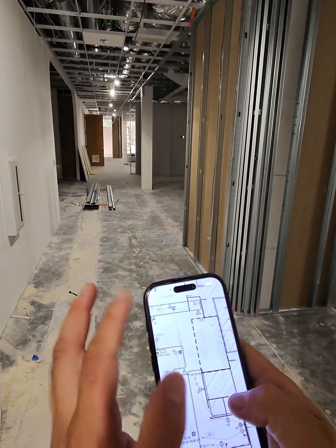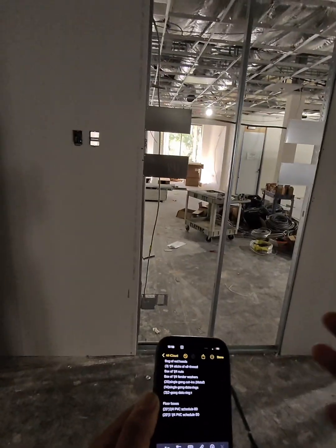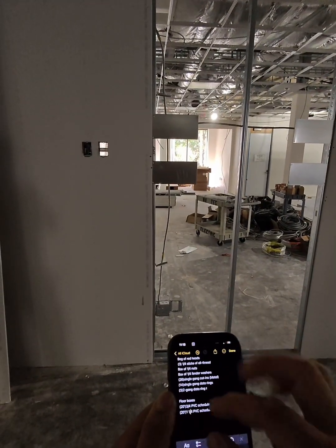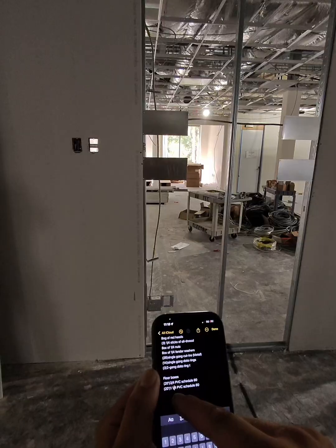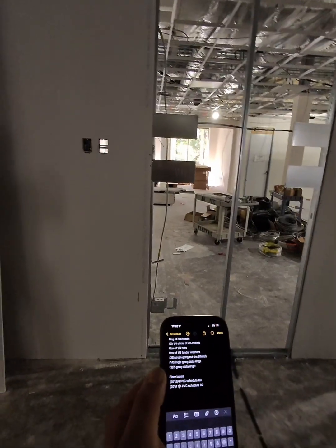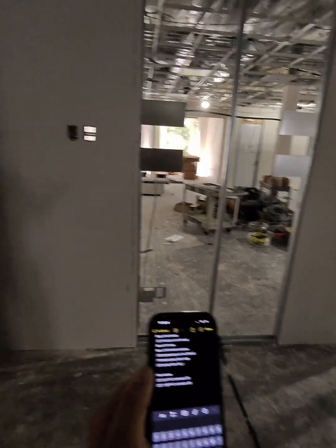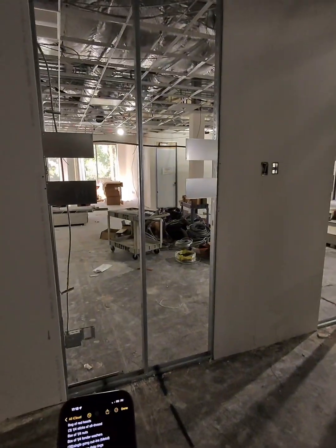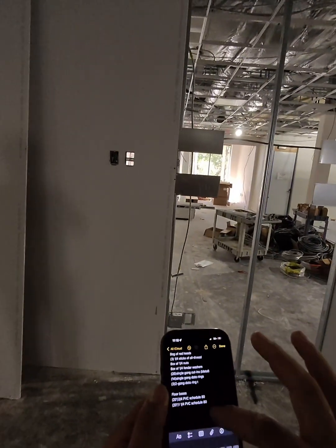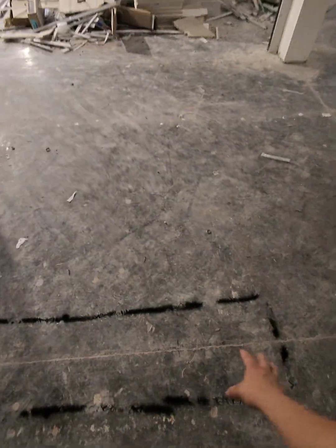And then there's a note on this page. You can kind of get creative in the way you write it. Here I'm putting 20 feet, 3/4 PVC schedule 80, 20 feet, 1.25 PVC schedule 80. But you could put 2 sticks instead of that because the sticks are 10 feet each. I've liked to start doing it like this. And the floor box is gonna go right here. So I need one connector of each, but then I need another connector of each to go inside the box.